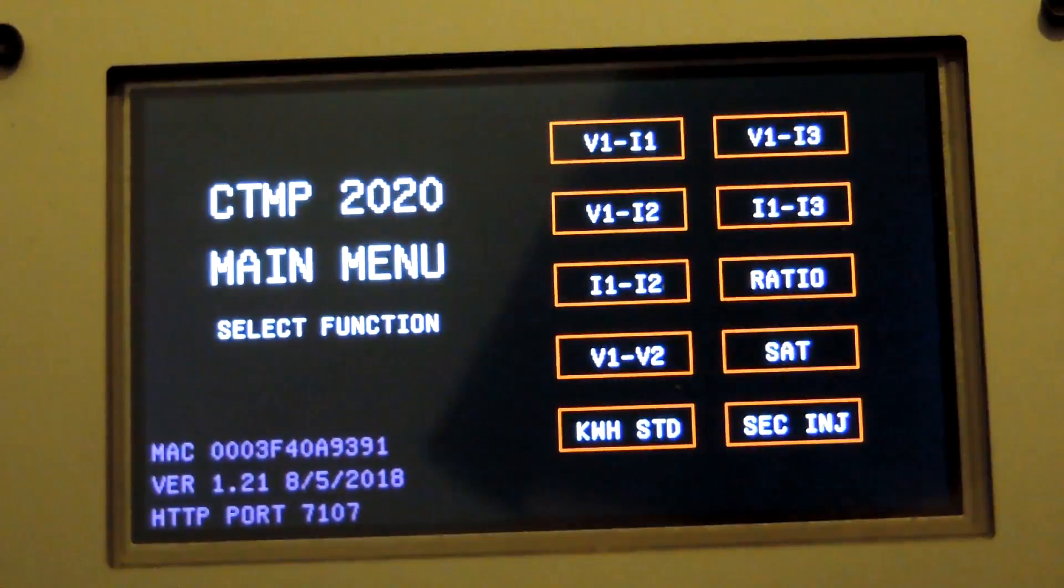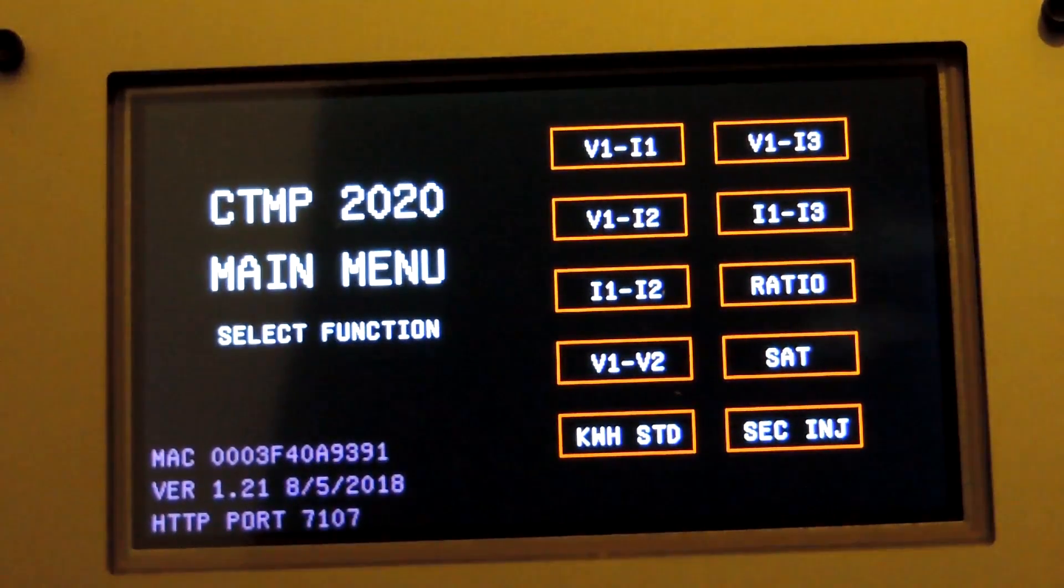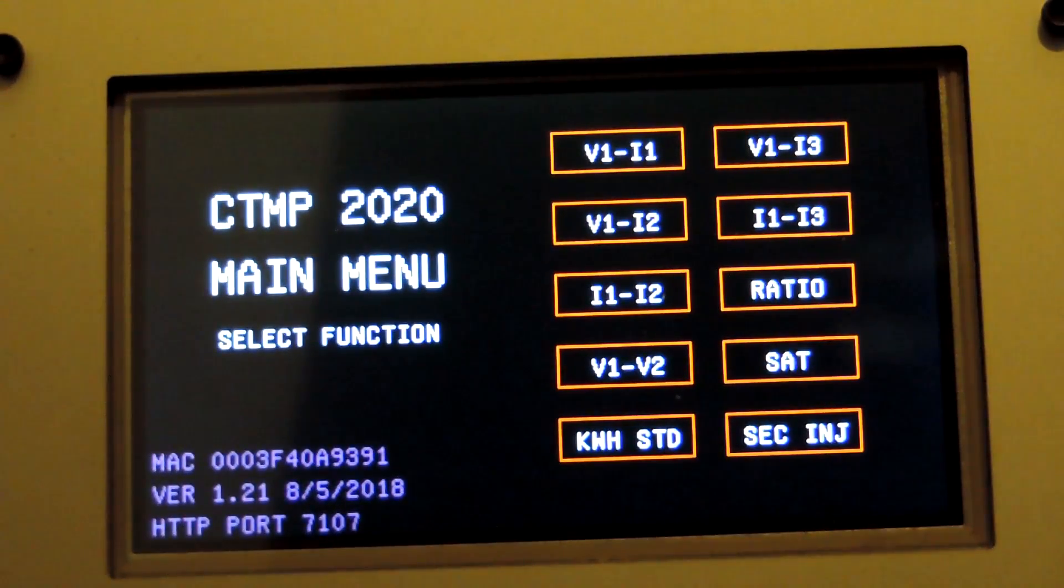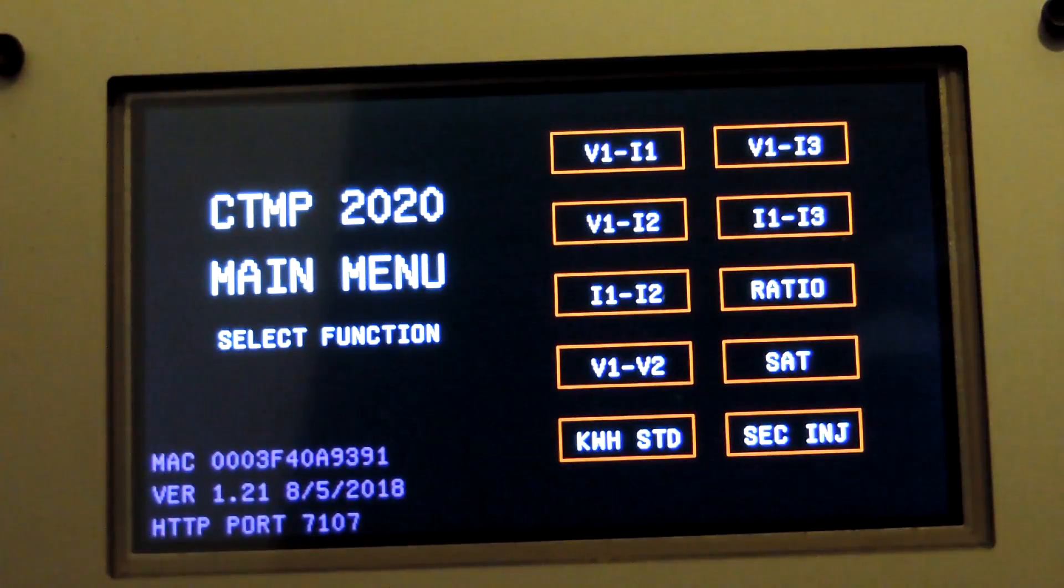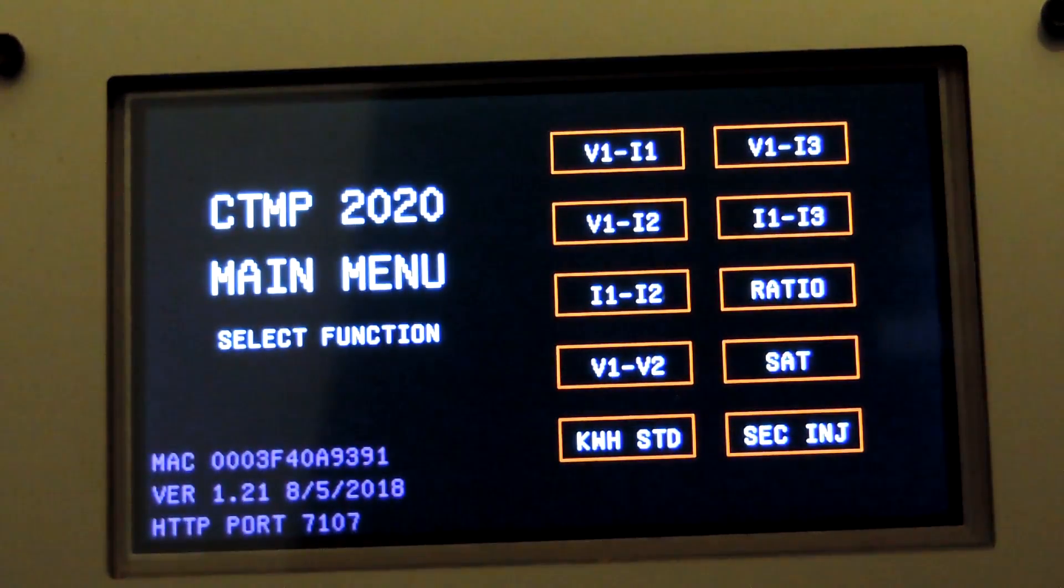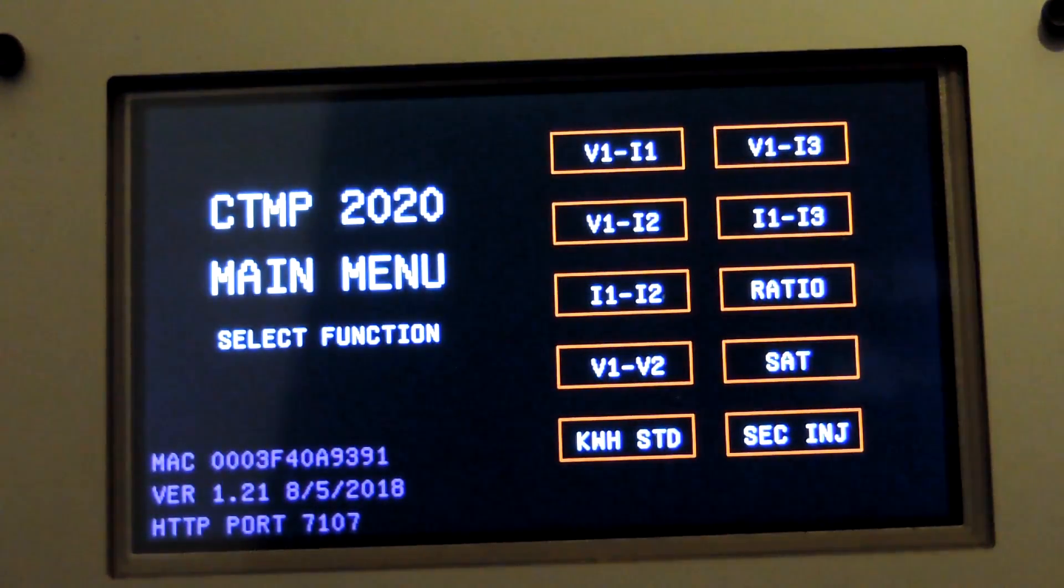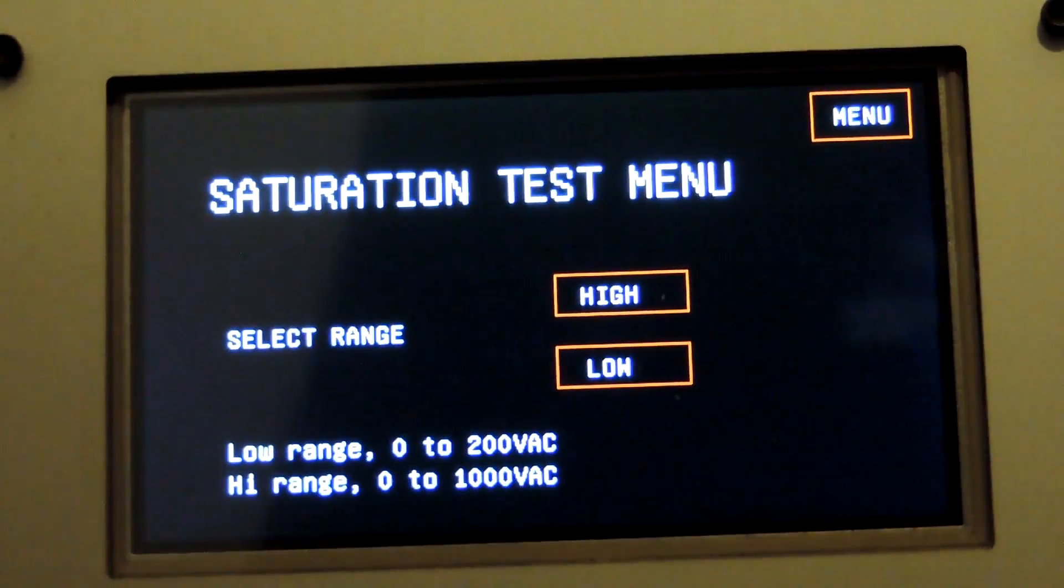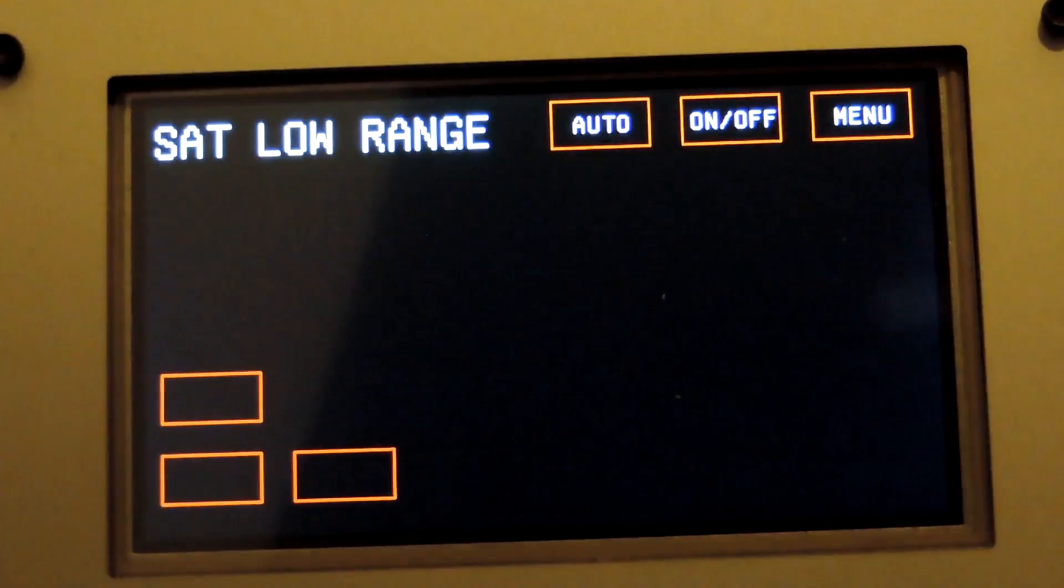Okay, this will be a demonstration of the two terminal secondary saturation test. It's connected just like the two terminal ratio test, so I won't have a show and tell on the connection. I'm going to press saturate, I'm going to press low range, so I know it saturates below 200 volts.